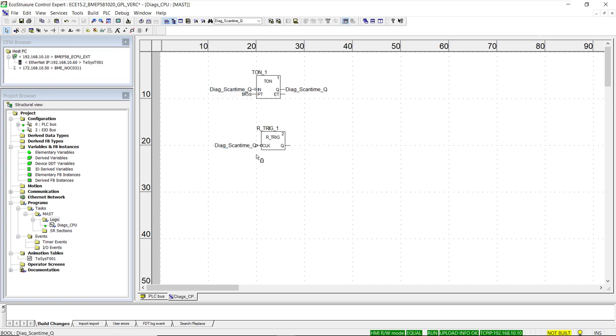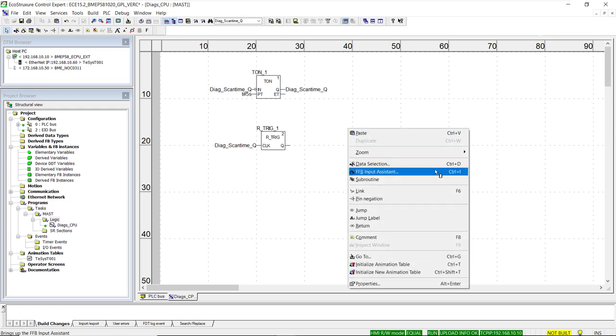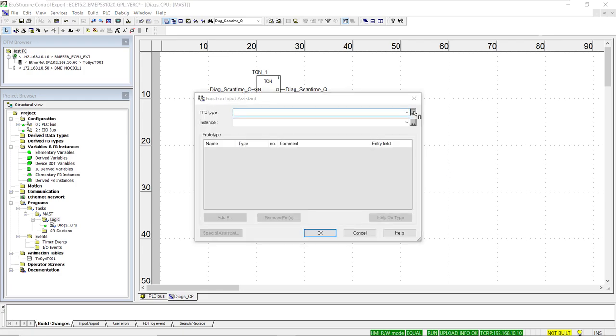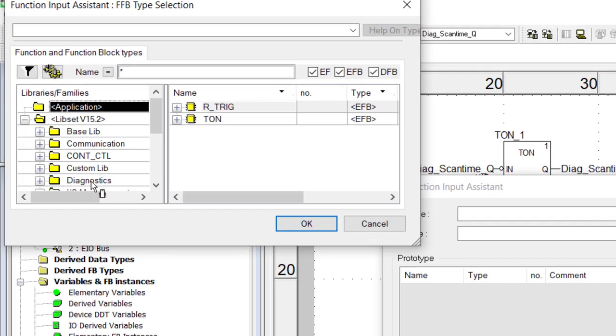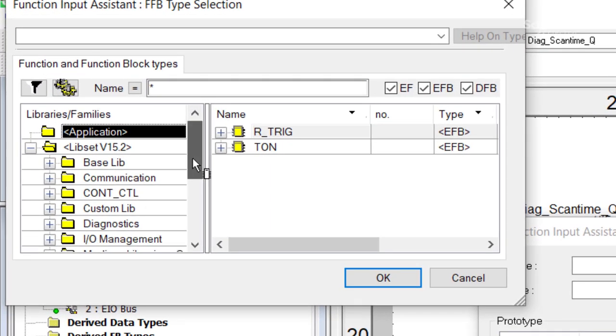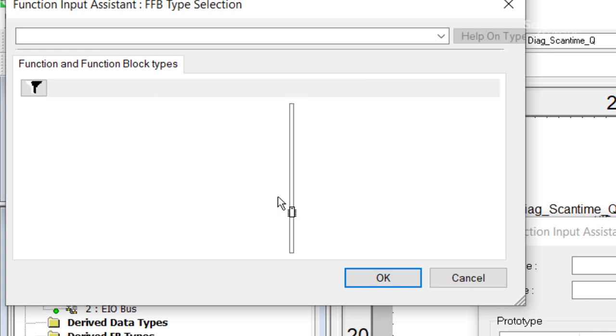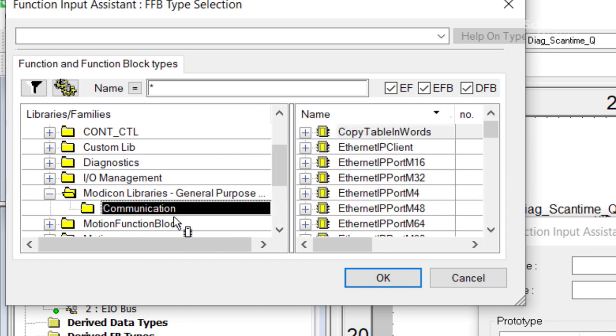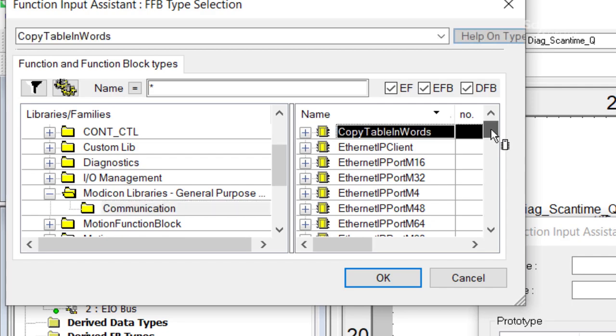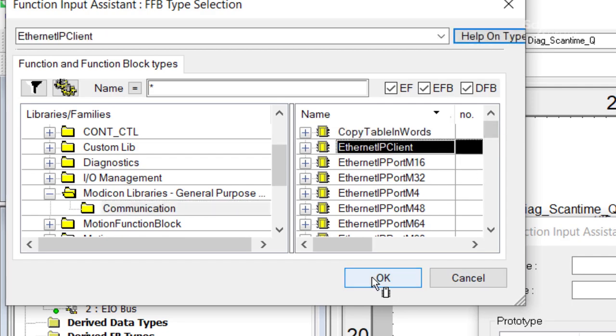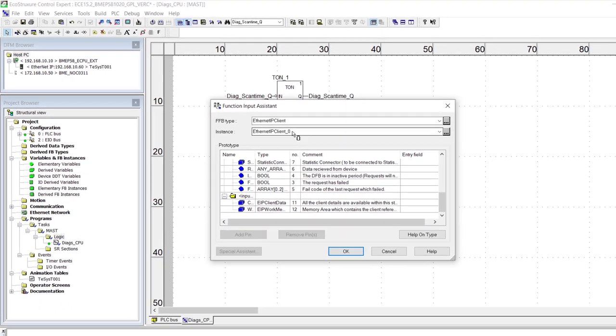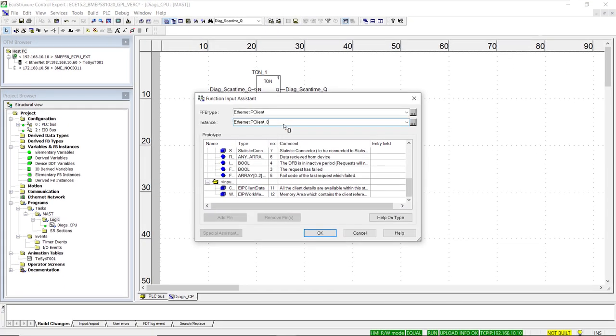A rising edge detection function block is used to trigger when the timer reaches its preset value. This signal then triggers the client function block from the GPL, which we add using the function block input assistant by navigating to the general purpose library folder, then the communications folder. There is only one Ethernet IP client function block, which we add into our logic.